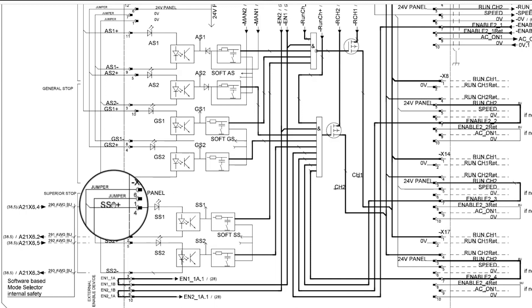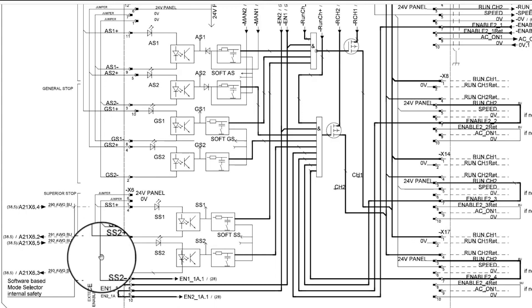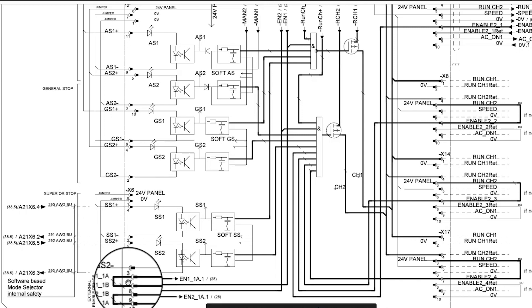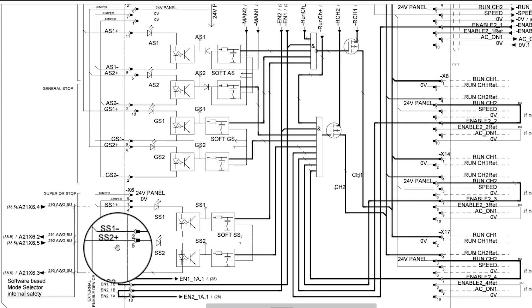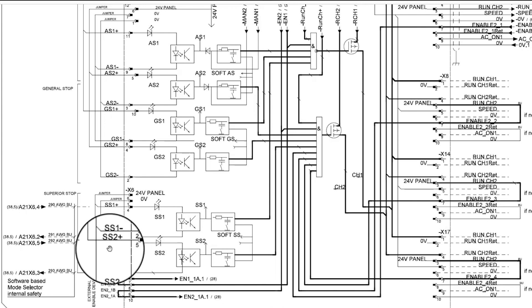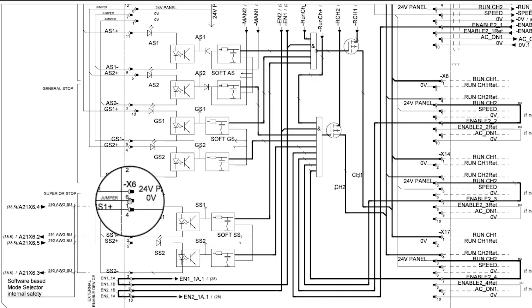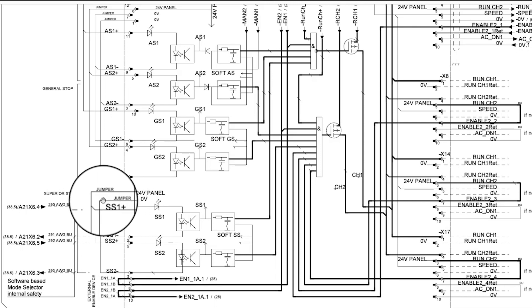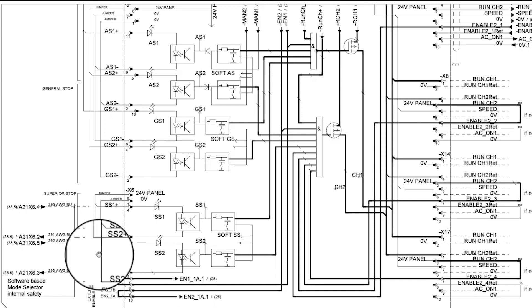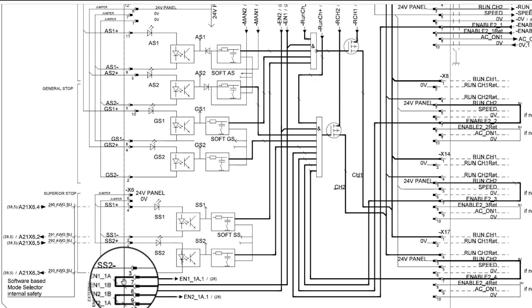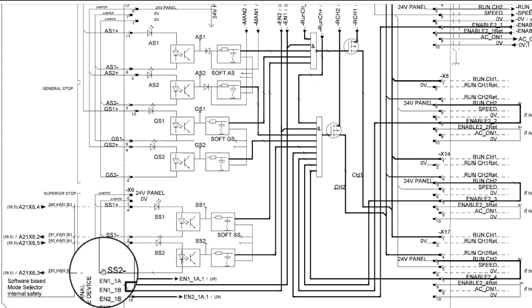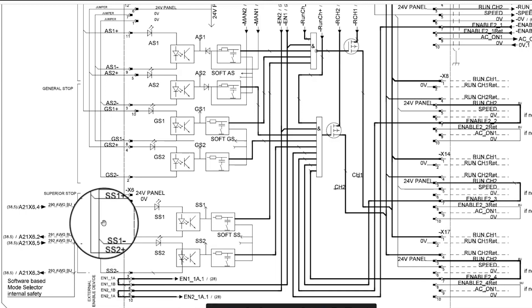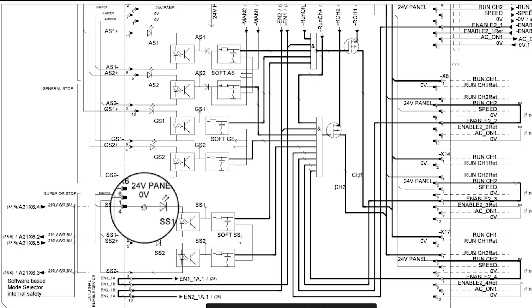If we look at SS1 and SS2 channels, you will see a very similar circuit. On connector X6 position 5, you will see SS2 positive is being supplied 24 volts from position 6 with the factory jumper installed. SS2 negative is located on connector X6 position 3. When the factory jumper is installed, SS2 negative will be getting its 0 volt circuit from X6 position 1.